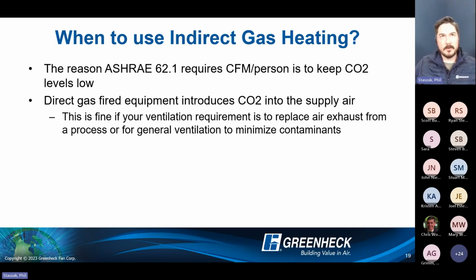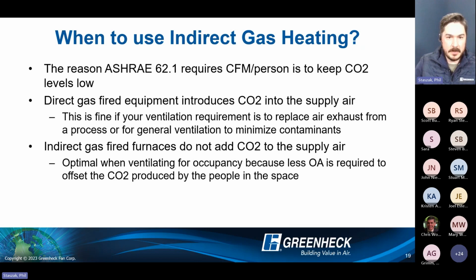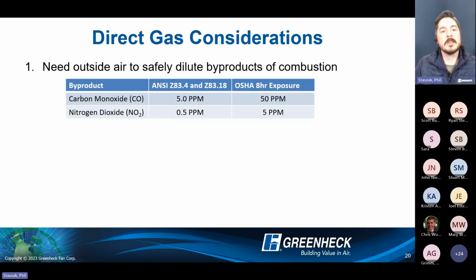The reason you have makeup air is that everything is vented outdoors as part of the process exhaust system. Now, indirect gas fired obviously doesn't add CO2 to the supply air, but one thing to consider, if you're talking about greenhouse gases, is a totally different conversation. Indirect gas fired at 81% efficient actually throws more CO2 out than your typical direct gas fired unit would. So outside air safely dilutes the byproducts of combustion.